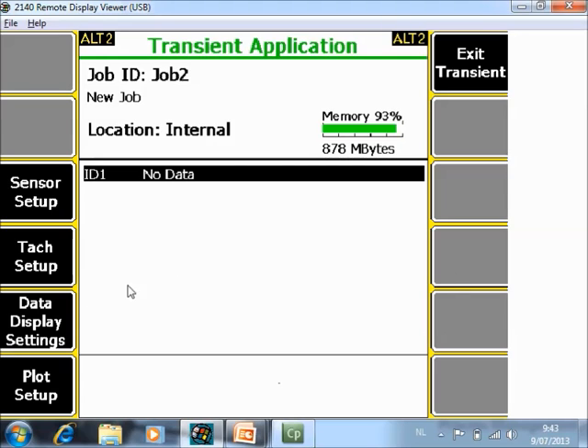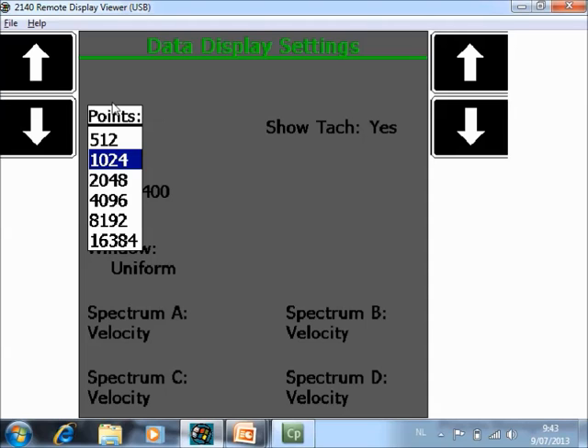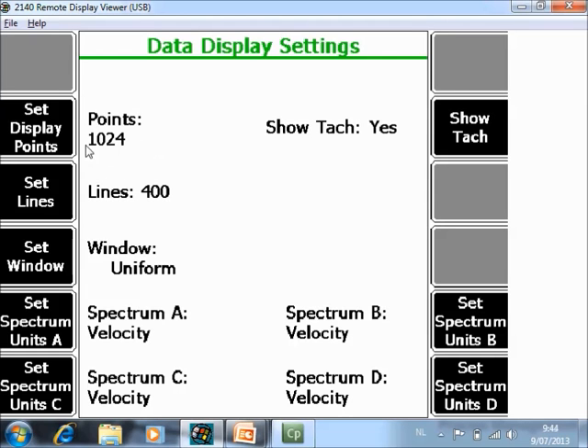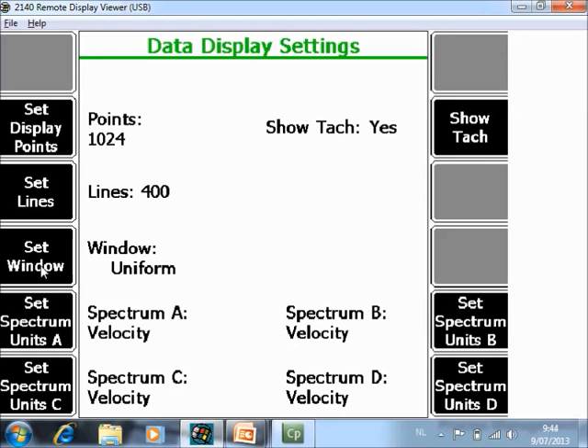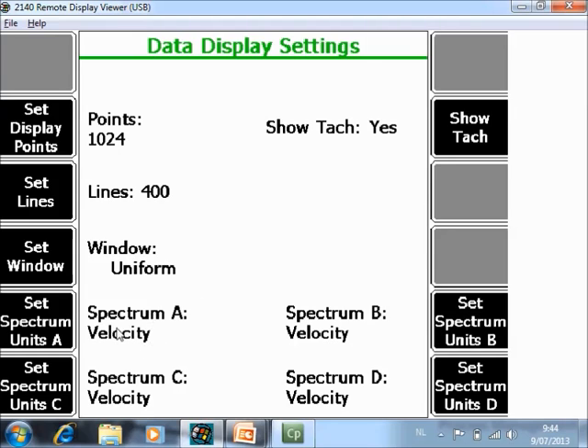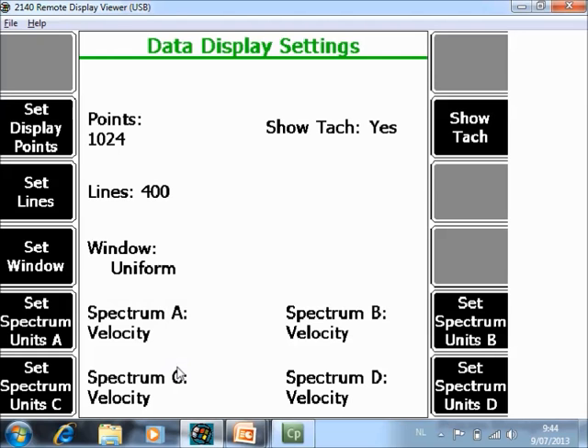Data display settings. Here you specify if you have a detailed waveform, how many data points do you want to see. On the spectrum, how many lines do you want to have. The window type, do you want to have uniform or hamming. And the units for your 4 channels in the spectrum, do you want to have velocity or something different. You can choose between acceleration, velocity, or displacement. And last, if you have measured a speed pulse as well, do you want to see the tach lines on the spectrum, yes.